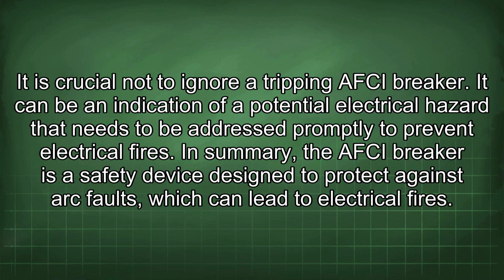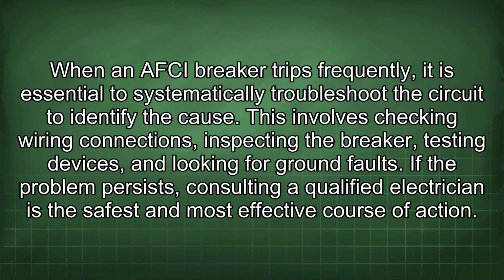In summary, the AFCI breaker is a safety device designed to protect against arc faults, which can lead to electrical fires. When an AFCI breaker trips frequently, it is essential to systematically troubleshoot the circuit to identify the cause. This involves checking wiring connections, inspecting the breaker, testing devices, and looking for ground faults. If the problem persists, consulting a qualified electrician is the safest and most effective course of action.